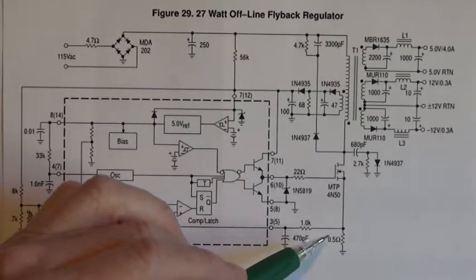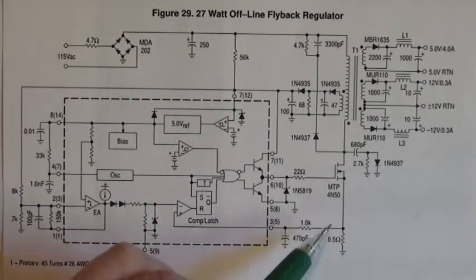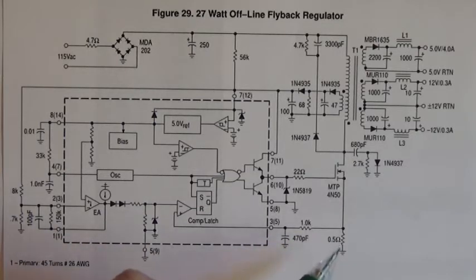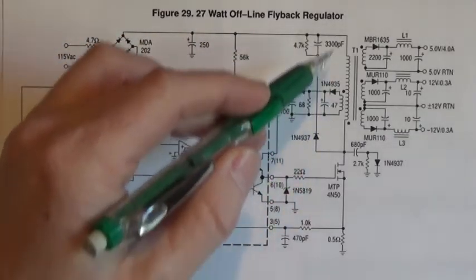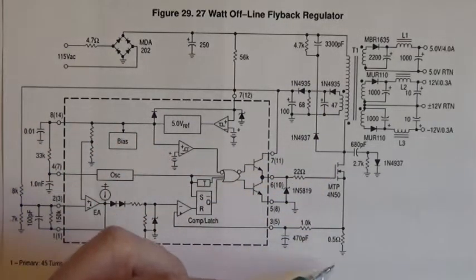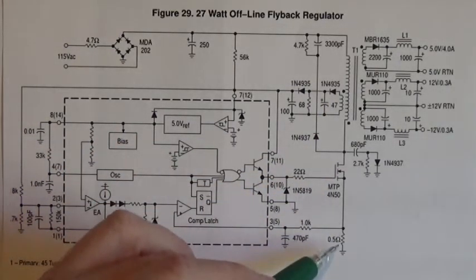you want to check this current feedback resistor right here and make sure that it's not opened up because you have large amounts of current flowing through this shorted device through that 0.5 ohm resistor and that will open up.